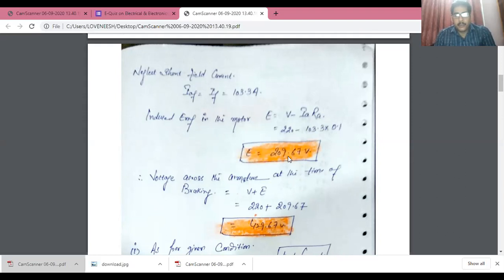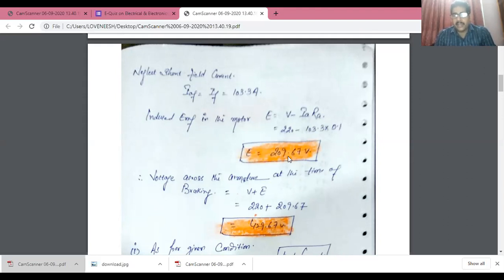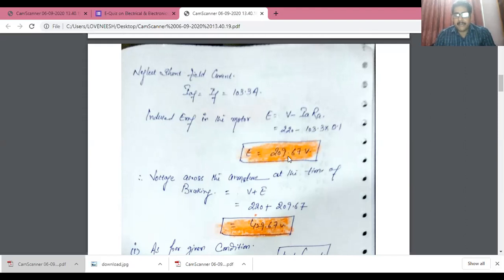Using the back EMF formula: E = V − (Ia × Ra). Brush drop voltage VB is not given, so we assume VB = 0. Substituting: E = 220 − (103.3 × 0.1) = 209.67 volts. The voltage across the armature at the time of braking equals supply voltage plus back EMF: 220 + 209.67 = 429.67 volts.